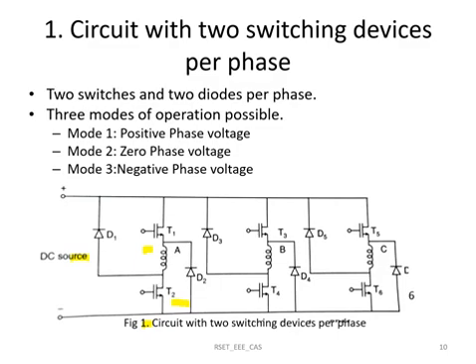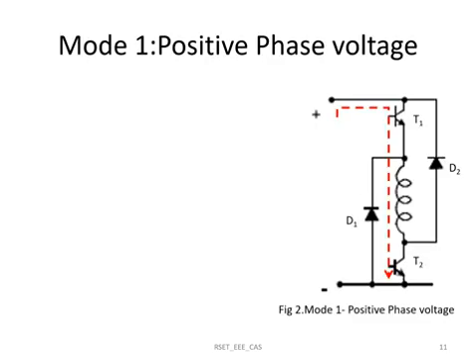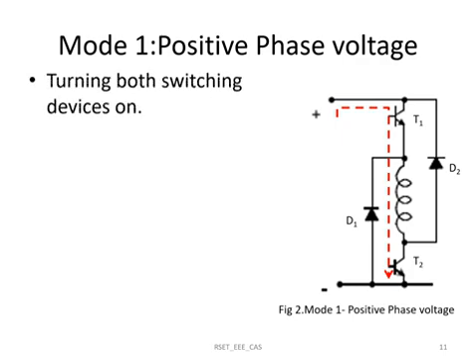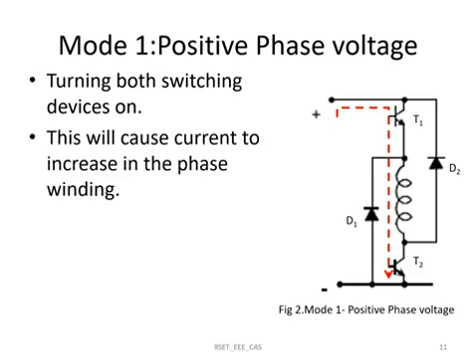The working principle involves three modes of operation: positive phase voltage, zero phase voltage, and negative phase voltage. In mode 1 (positive phase voltage), both switches T1 and T2 are turned on and current starts to flow from the supply to the winding. Energy is transferred from the supply to the winding through switches T1 and T2, and the current in the phase winding increases.